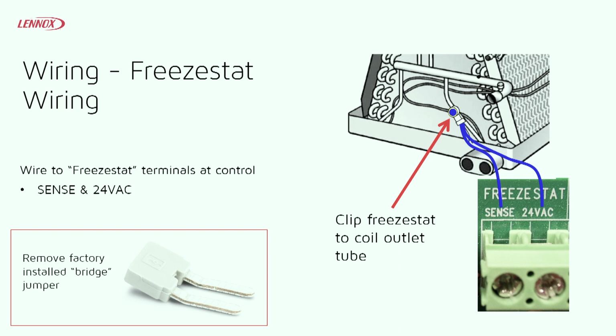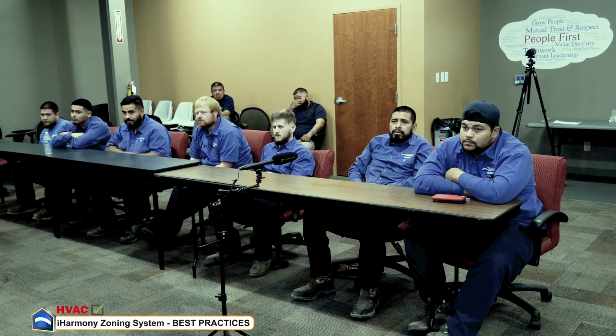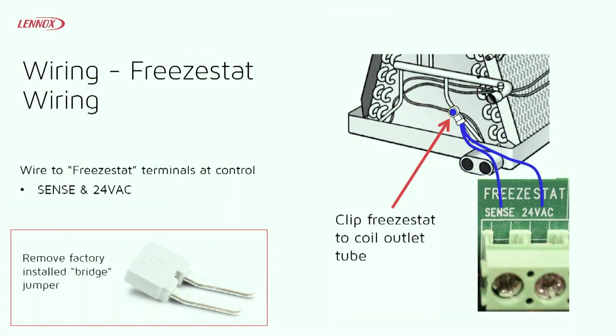So if you want to connect the safety switch, and if it's communicating, you don't want to cut the R, or is that okay? That's a good question. With a safety device, that can be installed. We have a separate diagram for that. I don't think I've got it covered in here, but that's something I can send to Uwe that he can share with you guys. What we recommend doing is using an isolation relay and having that break the common wire to either your outdoor unit or your smart hub.